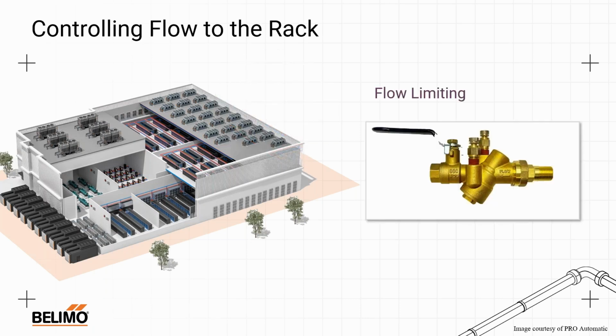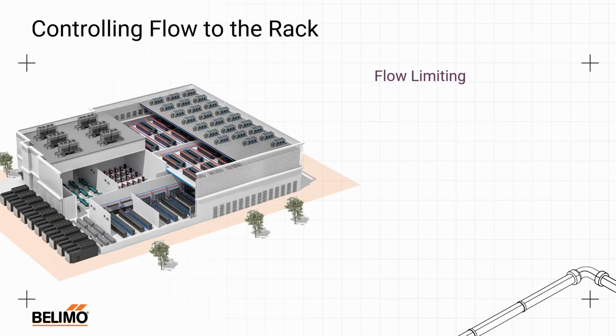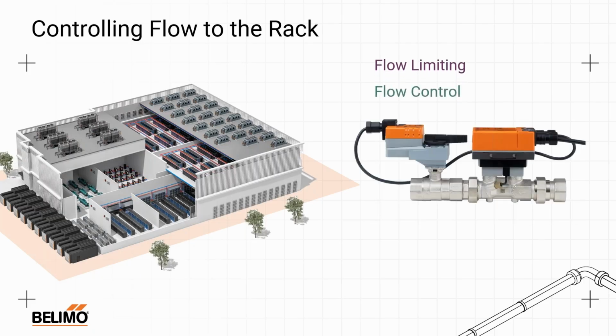The simplest option and the most basic way you can control that is to simply put a flow limiting device on there. If you know that your rack requires, say, 10 gallons per minute, I'm going to get a flow limiting device, set that for 10 gallons a minute, or purchase it based on 10 gallons a minute. And then I install that on my loop, and that's the simplest way. It's not providing any feedback or information. It's not terribly versatile in terms of its ability to change, but it does an excellent job of maintaining specific flows. So that would sort of be our low-tech solution.